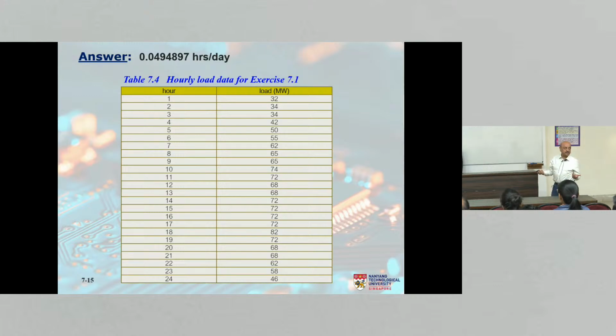Because the data is for 1 day, it will be hours per day. I remind you again, this is a time unit, this is a time unit. You can actually convert the hours to days, so it will be days per day. And then what will you get? Loss of load probability, LOLP, right? The two are related. However, this is more meaningful. You and I can relate to it, right? How many hours am I not going to get supplied today? 0.049 hours, right? Whereas if I say the probability of not being able to fulfill the load today is 0.98, that is not so meaningful, right? So the two are related and yet this is more significant.